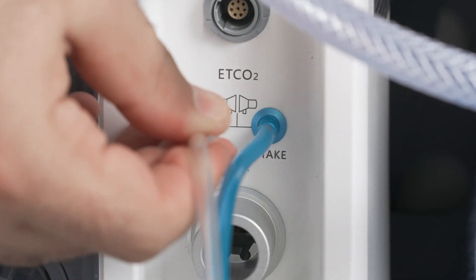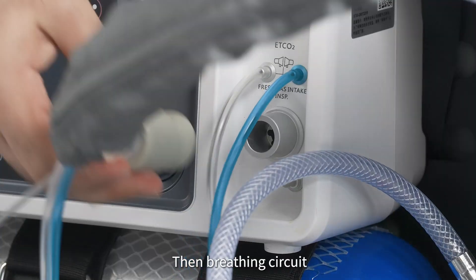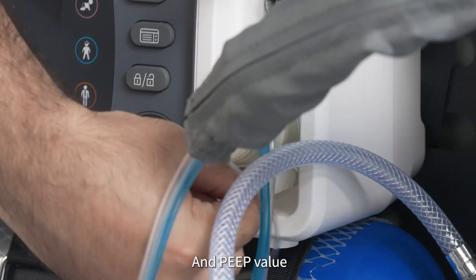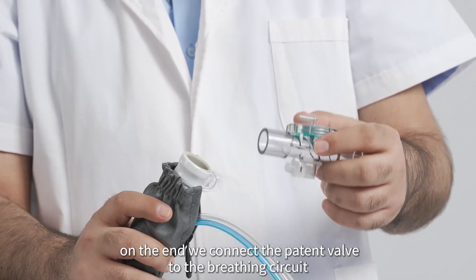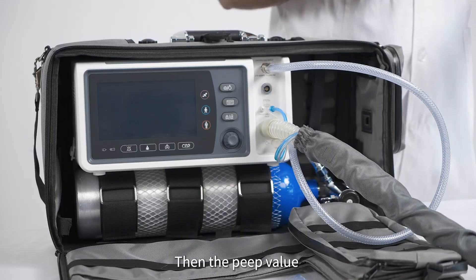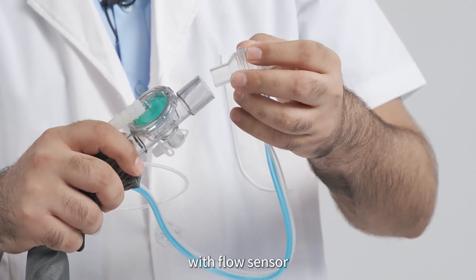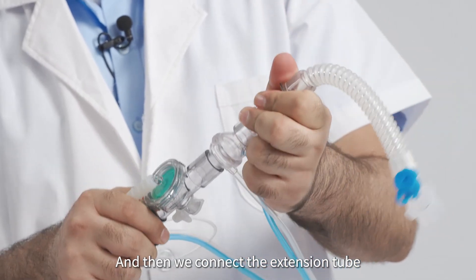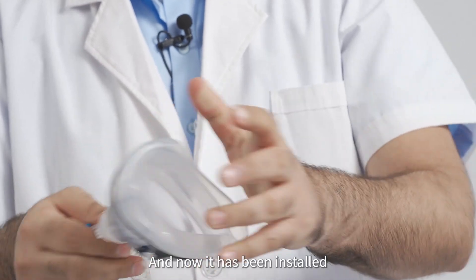Connect according to the colors: blue into blue and white into white. Then connect the breathing circuit and PEEP value. Connect the patient valve into the breathing circuit, then the PEEP value with flow sensor. Then connect the extension tube and the patient mask. The device is now installed.